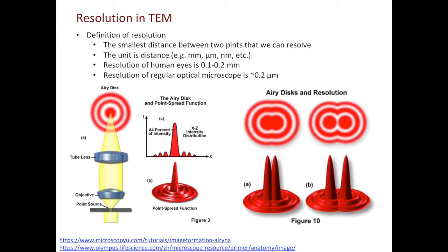Here, I'd like to elaborate a little bit on what happens when we focus the beam to the smallest spot. When you converge or focus the beam to the smallest spot, you actually do not get a spot. Instead, you get a disk. The name for the disk is called the airy disk. The reason we do not get a single point or spot is because we cannot converge the beam to a smaller size than its own wavelength. You can also see the concentric rings around the airy disk. The distribution is described by the point spread function. Therefore, to be more accurate, resolution should be defined as the smallest distance between two airy disks instead of two points that we can resolve. In the example here, it is more difficult to resolve the two airy disks on the left, but much easier to resolve the two airy disks on the right.